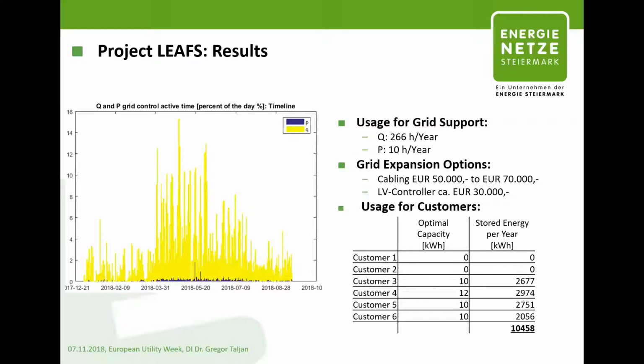Perhaps just a short overview of the results. We've seen that the storage with real power is only used for 10 hours a year. So it's a big asset, but we don't use it very often. What's very important, and what I'd like to stress, is that reactive power is of great use for us as DSO. For 370 hours a year, the storage inverter is used for grid control, but with reactive power, not real power. So we don't need to put energy into the storage and take it out. For us, it's already a big advantage that we have an inverter with this reactive power capacity.